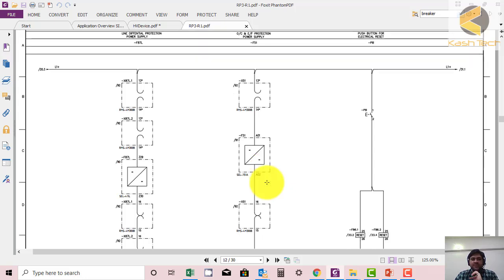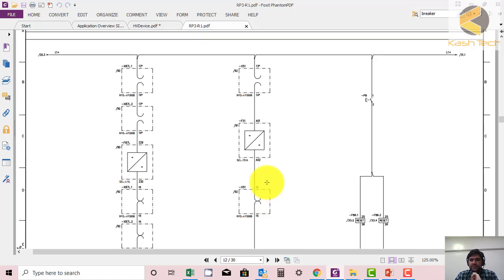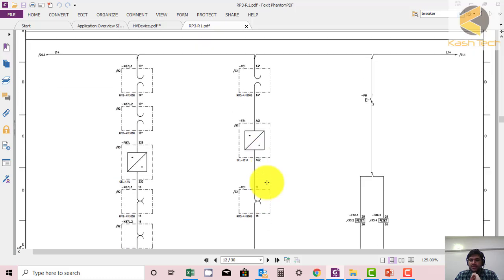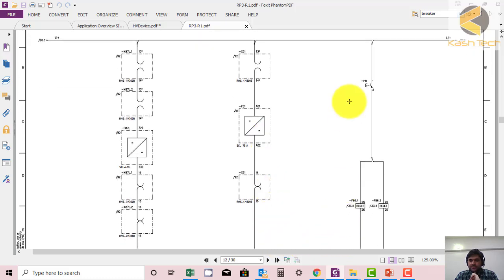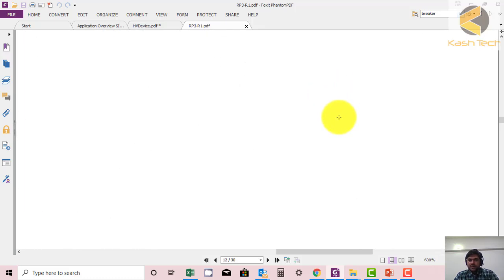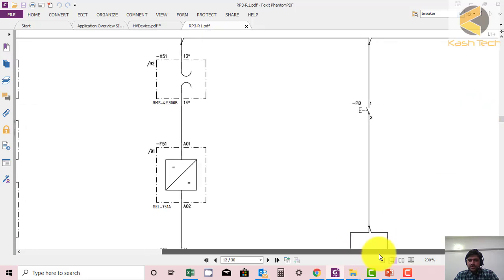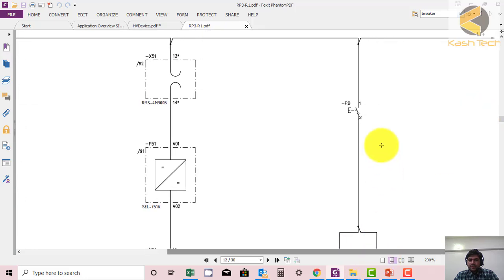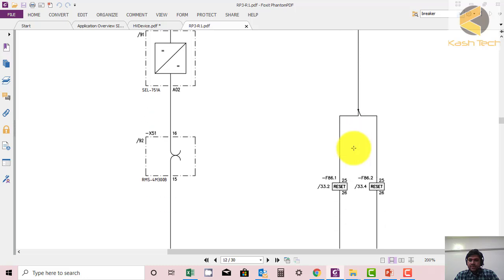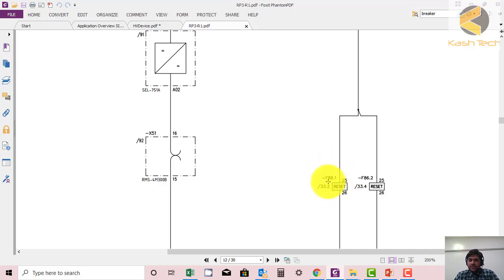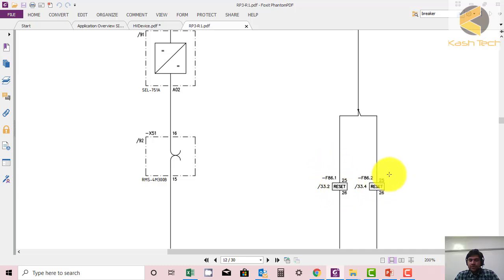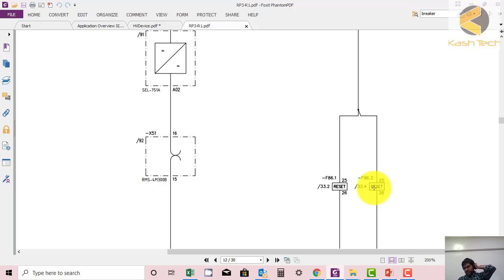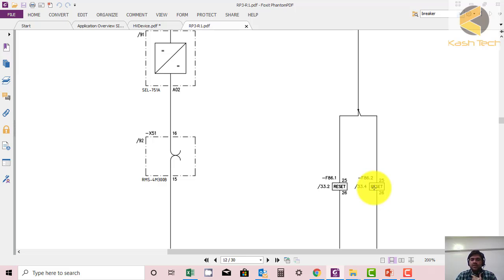This is the push button PB. Let me zoom this symbol for you. This is a push button. When you push it, F86 - if you remember from your previous training - is a lockout relay. It will reset lockout F86.1, F86.2 is lockout 2. What is the purpose of lockout? The main purpose is when it operates, it will lock its position and will not reset automatically, and it will block the closing of the breaker. It will lock the breaker. We will discuss this in detail later.